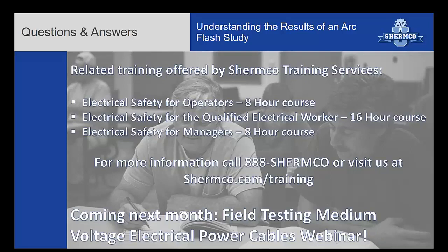Yeah, and if it's pulling cable into an energized 480-volt panel board, if that was your task that you just felt you had to do energized, you know, rubbering off where you can, and then also teaching people how hazardous it is, what you've got to do, maybe having a watch to make sure someone's not veering off of what the task is intended to do. You know, those are all very tough decisions. We'd always prefer to do it de-energized, but sometimes that's not possible. And then getting a qualified person, having written procedures on exactly what has to be done is definitely one of the keys. Exactly.